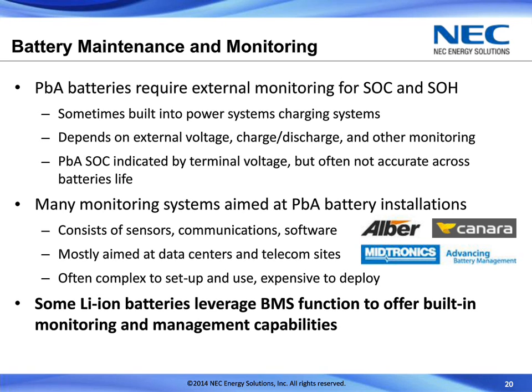There's actually a significant industry of companies, some examples shown here, who are providing monitoring systems, including sensors and communications and various analytics software, to provide some idea of what the actual state of health and operation of those battery banks are. On the other hand, some lithium-ion batteries actually have some of those functions built into extensions of their battery management system, and it can offer built-in monitoring and even communications built into the battery itself, so that this information can be looked at at the cell level inside that battery. So just something else to consider. It's not usually high on the list or something you think about with batteries, having a battery that might be intelligent, that can communicate this type of information and even provide some alarming associated with that. But it's something that's possible with lithium-ion batteries that is not really done with lead.